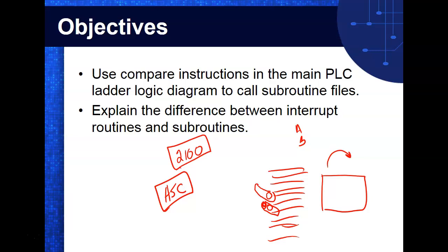Every PLC that I know of now has high-speed counters in it. And why is that? Because we're trying to keep up with all these encoders and all this stuff that's moving at such breakneck speeds that software counters just can't do it. You can only use 5 high-speed counters on this one, but you can still use the software counters. Yes. They're there and they're dedicated to certain inputs. But if you don't configure them, they don't work, right?